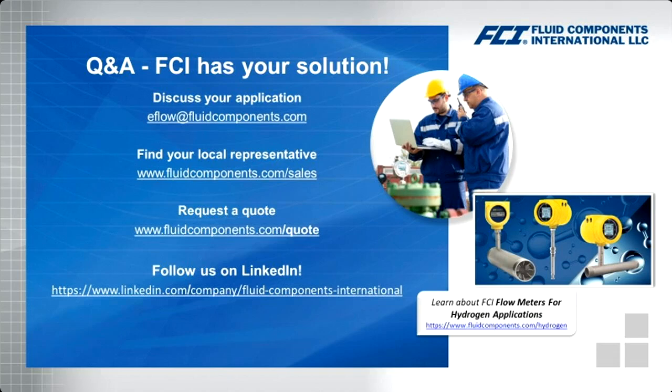All right, Brian, so a couple more before we wrap things up. If my process has times in which the hydrogen will contain some nitrogen, how will it impact the meter readings? Wow, another great question. If your hydrogen process occasionally contains nitrogen, it will cause small inaccuracies in the mass flow measurement. It depends on a lot of factors, right? How much nitrogen is present. If there's a high percentage of nitrogen present, yeah, you're going to see some inaccuracies. But because nitrogen and hydrogen are so far apart on the heat conductivity spectrum, the presence of nitrogen, although it does affect, has limited effect at small percentages.